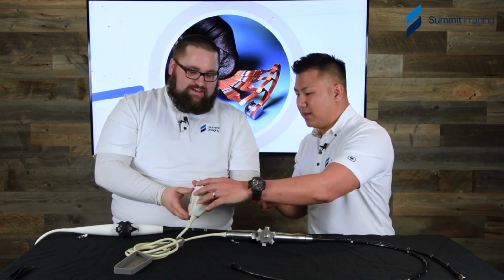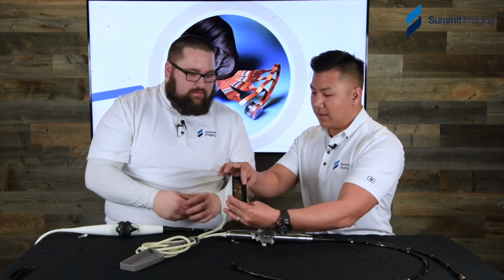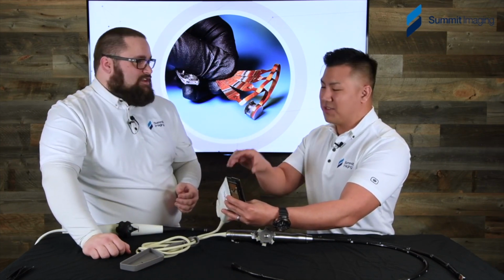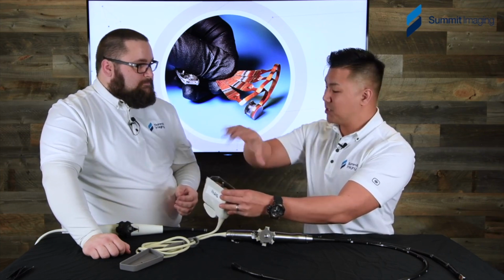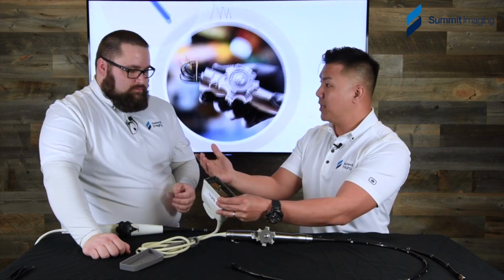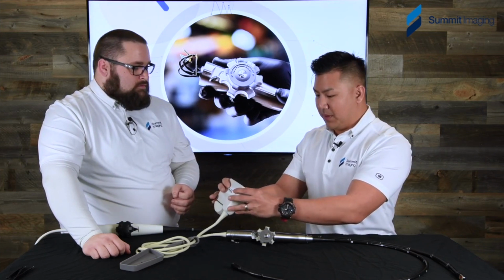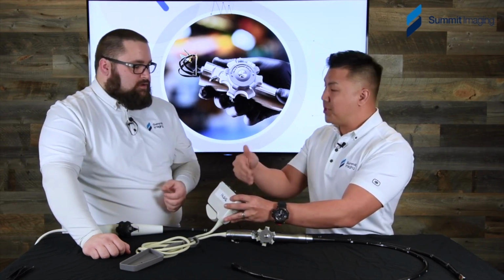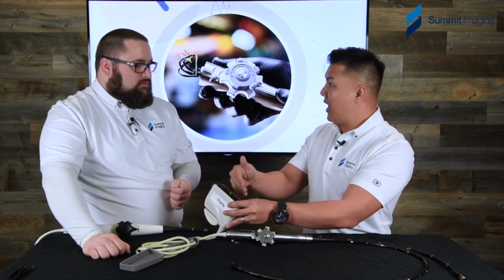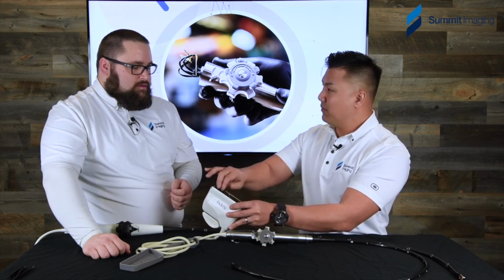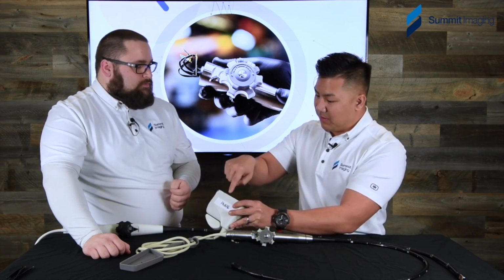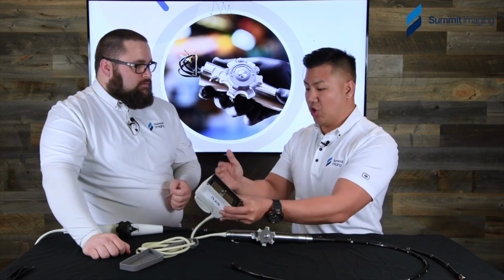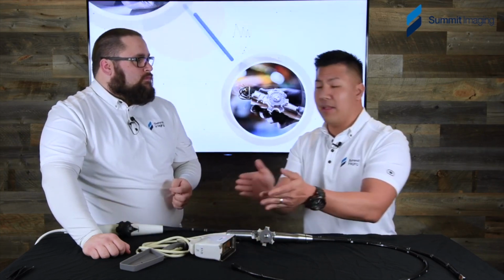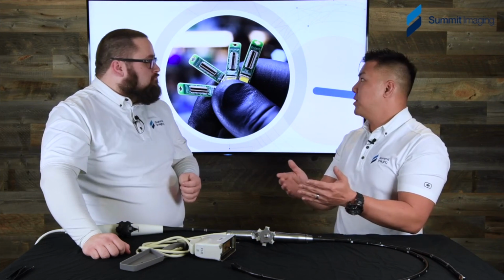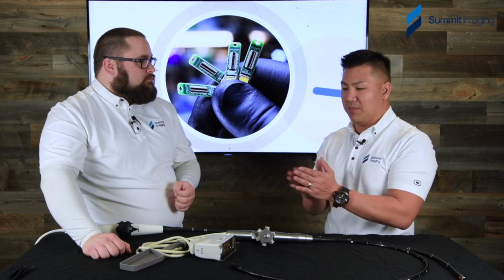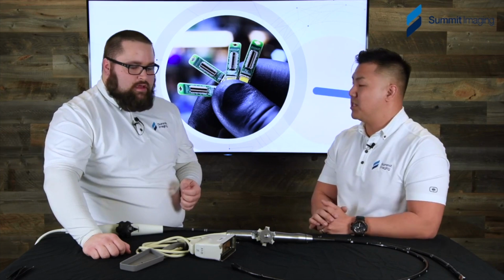I think we've also seen that if you look inside the connector here, there are no O-rings. Nothing. So when there's fluid intrusion into the connector, when somebody grabs it with a wet glove during sterilization or whatever have you, there's an opportunity to maybe clean it out with some paper towels or dry rags to cover the tracks. But the fluid is actually on the inside where all the electronics of the connector lie, and therefore can cause shorting. And we've seen shorts so severe that it actually blows traces inside the PCBs of the connector.